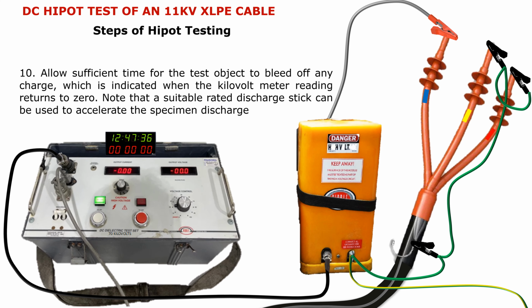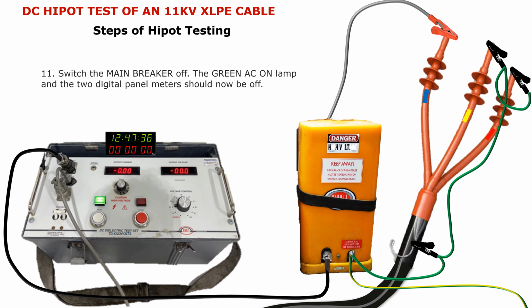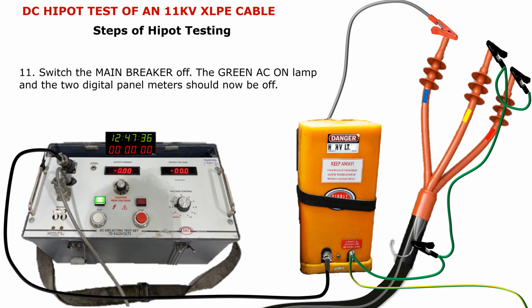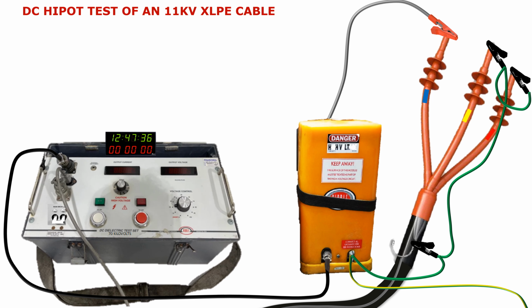Allow sufficient time for the test object to bleed off any charge, which is indicated when the kilovolt meter reading returns to 0. Note that a suitably rated discharge stick can be used to accelerate the specimen discharge. Switch the main breaker off. The green AC on lamp and the two digital panel meters should now be off. So, my dear viewers, this was the procedure of testing the Hipot high potential test of the cable.